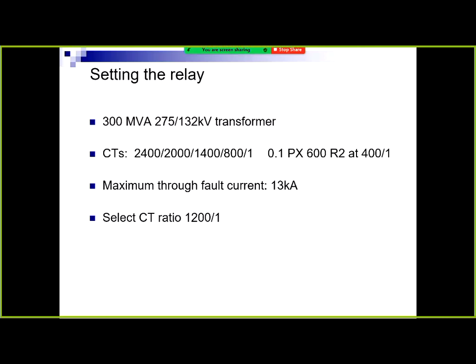The reason we do that at Powerlink is because these CTs we buy can go anywhere in the state and can have any ratio on them. If you're designing for a renewable connection or a mine site or a specific factory, you can get your ratio and just have a single ratio CT. That's what you're designing it for. When we order these, when we specify these, we don't know where they're going. It can be anywhere in the state. So we have a big range of that.